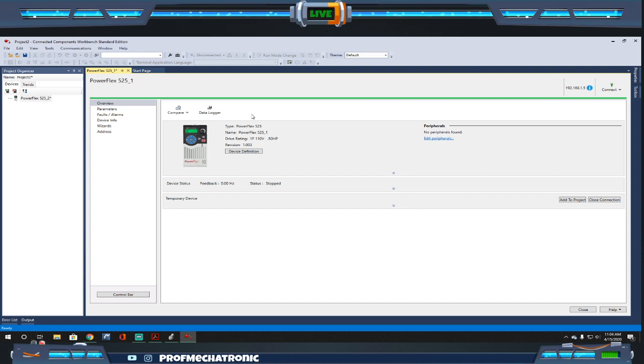Hopefully that answers the question about the cable used. Ethernet cabling and setup is definitely the easiest way to communicate to a VFD, and that's why I wanted to cover how to set that up - the basic configuration of the IP address on the drive, and running it over Ethernet to the PLC to pull that information in.